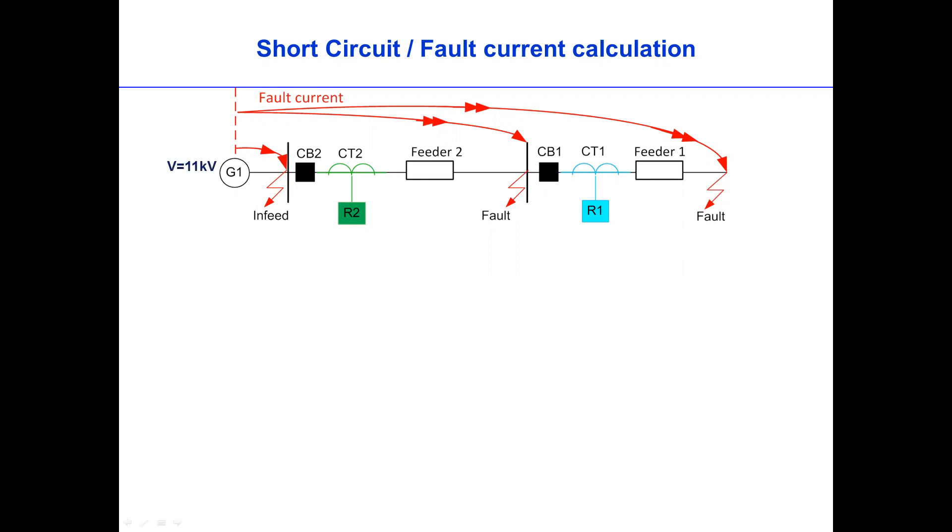The first thing we need to do is calculate the source impedance of the generator, how strong the generator will be, and the line impedance of feeder two and feeder one. If we have the line impedances and the source impedance, then we should be able to calculate the fault at each fault location.